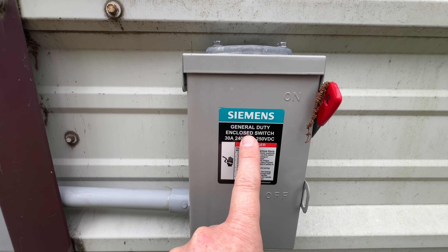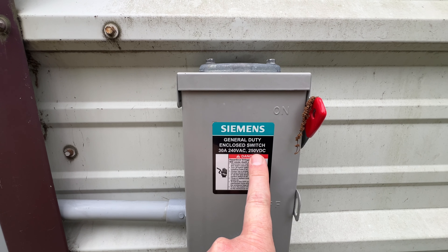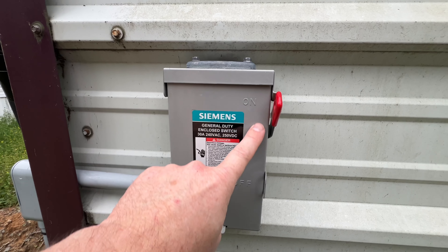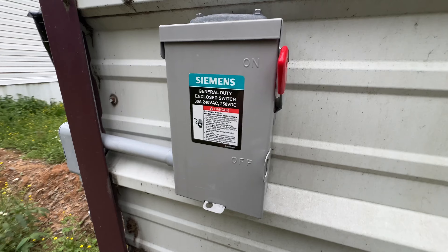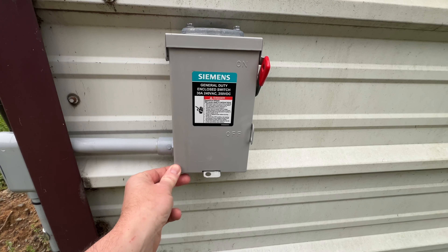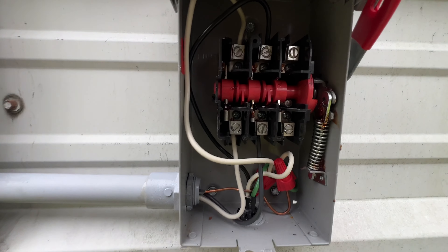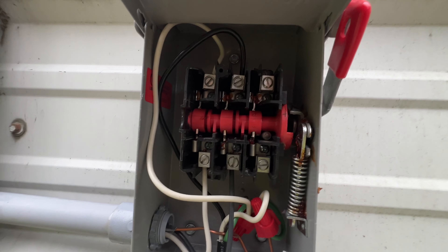The wire goes into this Siemens outdoor general-duty enclosed switch — 30 amp, 240V. This is what is required by the power company: it must have a lockable disconnect. This is a three-pole switch but you only need a two-pole. There are three spots inside — it's a physical air break.